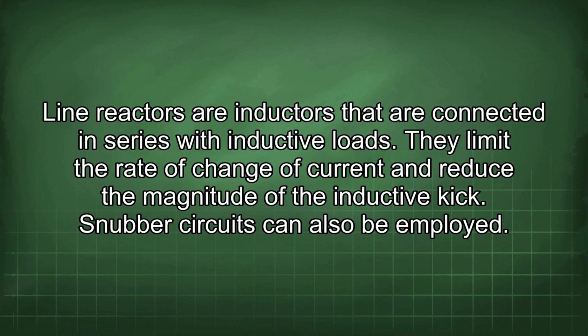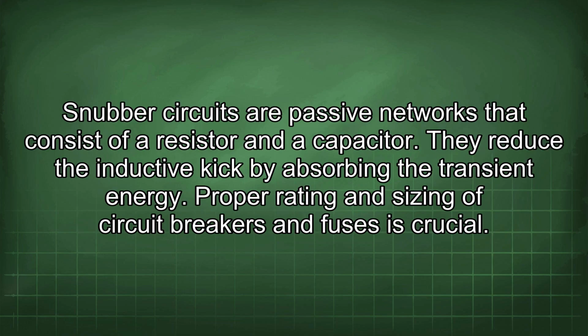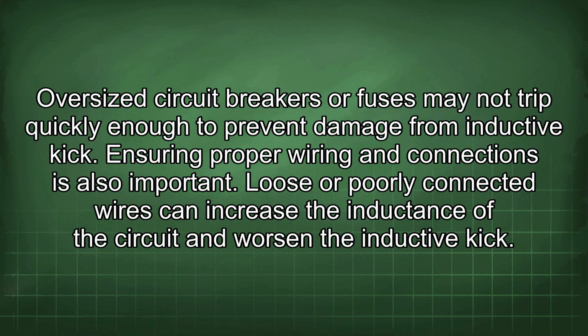Snubber circuits can also be employed. Snubber circuits are passive networks that consist of a resistor and a capacitor. They reduce the inductive kick by absorbing the transient energy. Proper rating and sizing of circuit breakers and fuses is crucial. Oversized circuit breakers or fuses may not trip quickly enough to prevent damage from inductive kick.